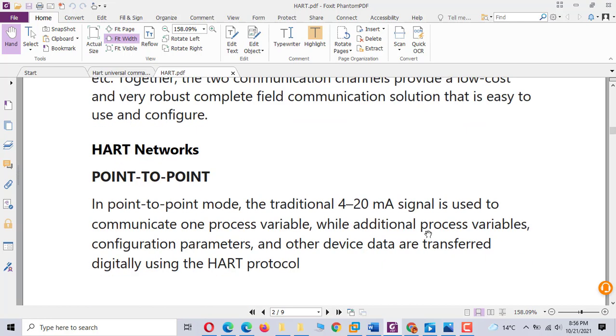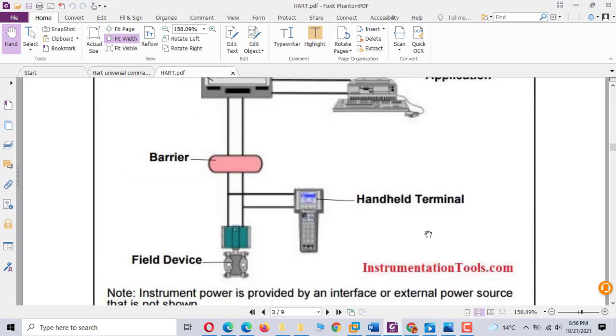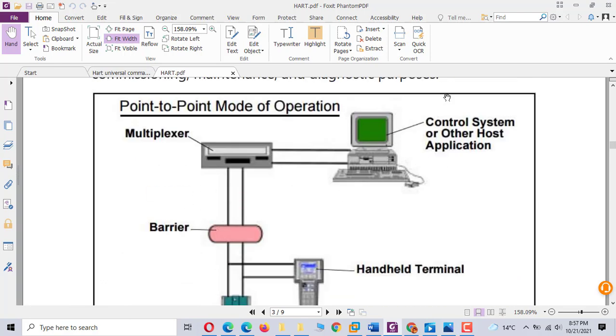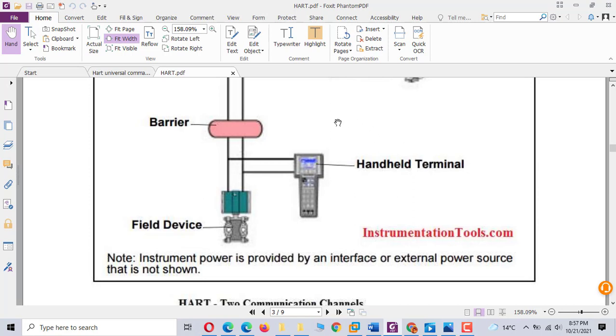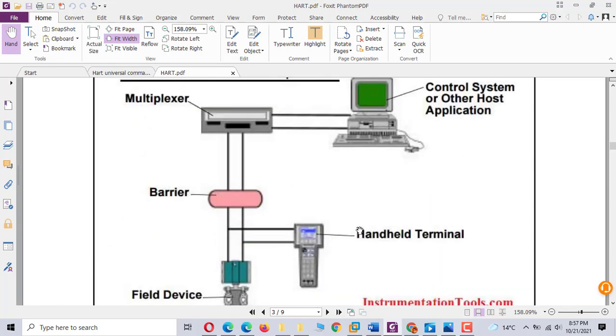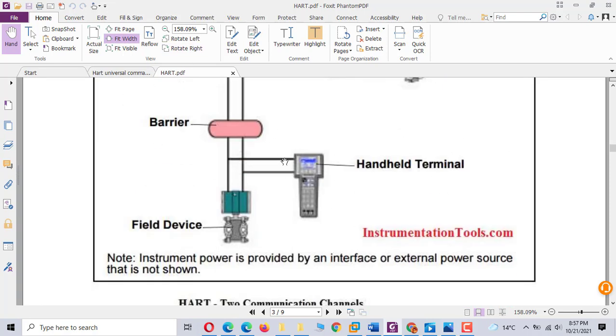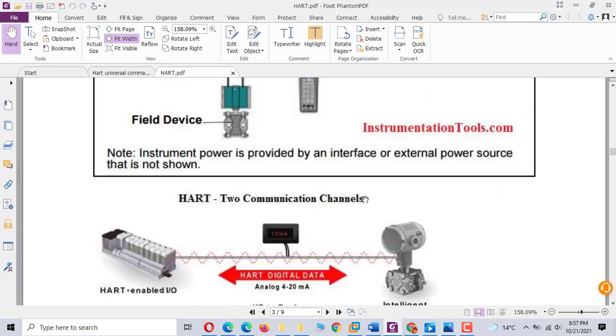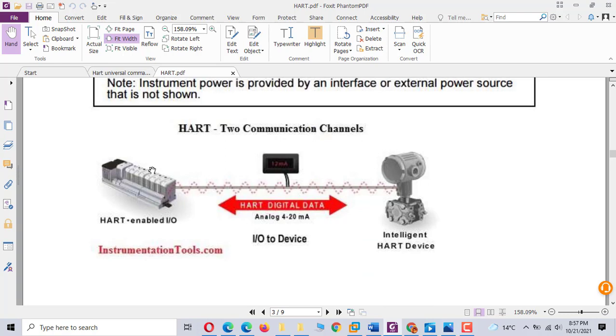The HART network has point to point, looks like this. This field device is HART, a slave. This master is the primary master. This HART communicator is called the secondary master. It doesn't matter which is first or secondary. But if you use a HART communicator, we can still do calibration and any configuration. Okay, this is HART digital data.